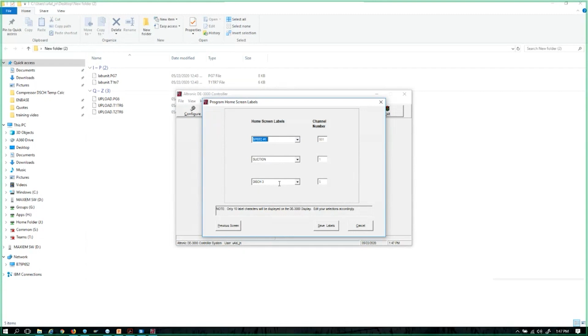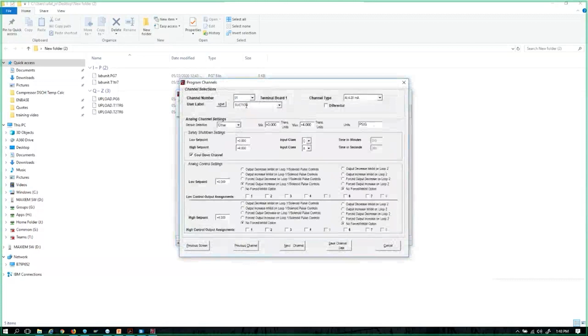On the new DE-3000, we do not use these pages to populate the labels on the DE-3000 screen. Instead, we use the labels from the channel section. The one confusing thing is that this section will let you enter almost 20 characters. But when this data is programmed into the DE-3000, it's going to cut you off after the first 9 characters, and that includes spaces. So it's really important with the new DE-3000 system to come up with abbreviations that are 9 characters, including spaces, or less.